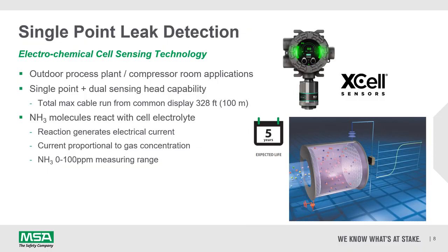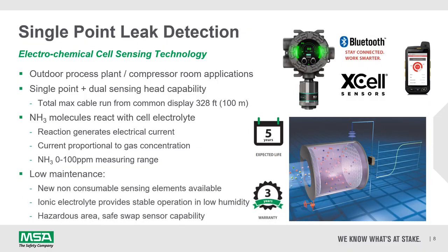The principle of operation is that ammonia molecules diffuse into the sensor head and react with an electrolyte. This electrolyte generates an electrical current which is proportional to gas concentration, and as a result you can achieve a measuring range of 0 to 100 ppm. However, this technology has been fraught with short sensor life as the electrolyte has been consumable, but recent advances in non-consumable electrolyte have resulted in a life in excess of 5 years. This same advance has also improved stability in low humidity environments.